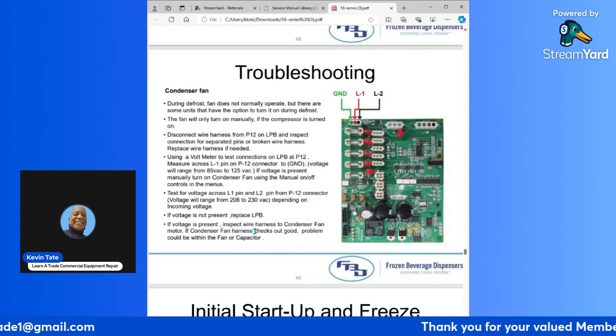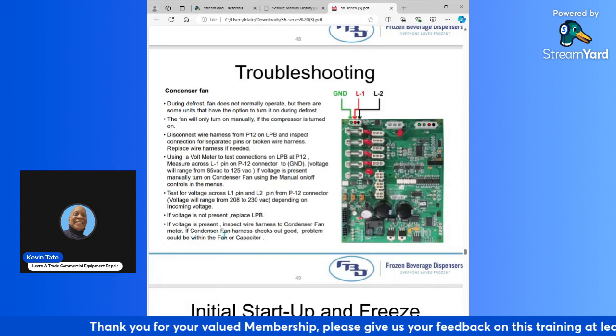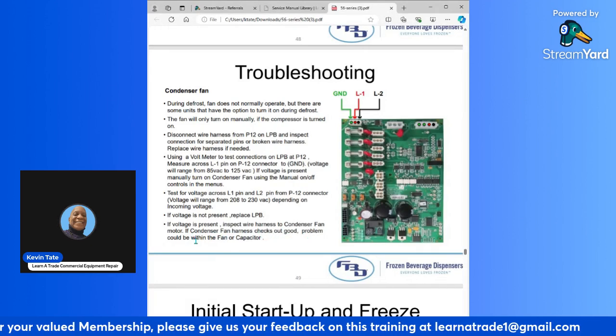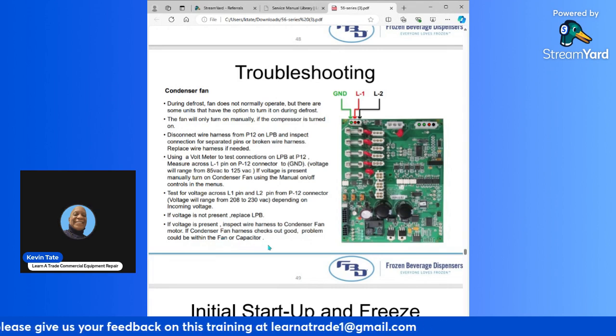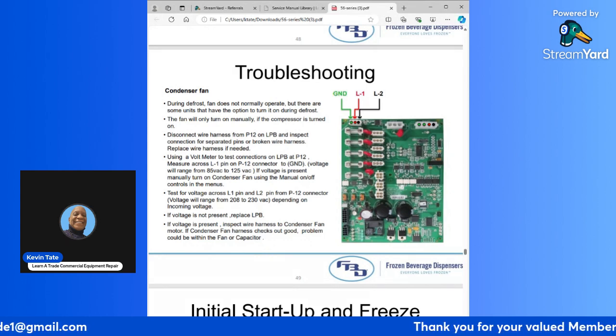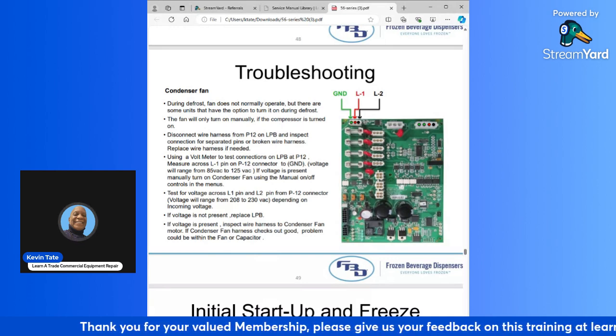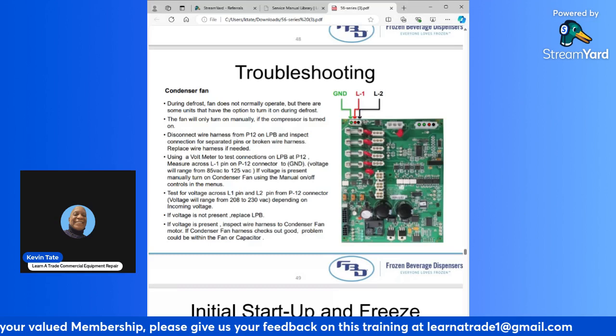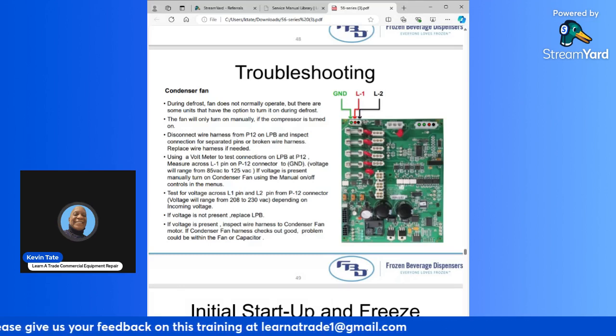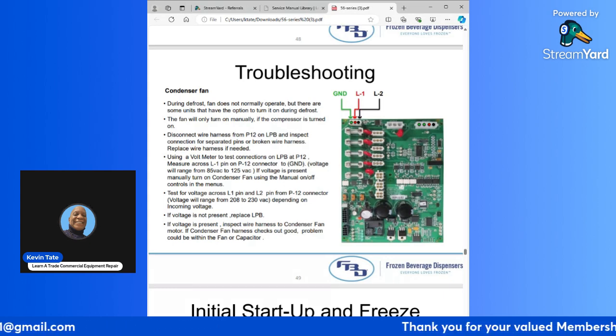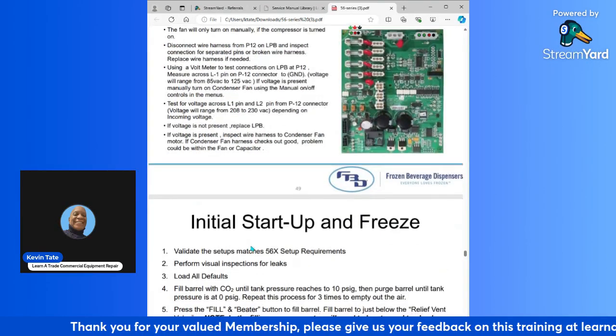If voltage is present, inspect the wire harness for the condenser fan motor. If the condenser fan harness checks out good, the problem could be within the fan or capacitor. So if everything else tests good, your voltage is present, and you inspect the wires and they all seem good, you could have an issue with the fan itself. The motor shaft could be bound, or you could have an issue with the fan capacitor, in which case you could just change out the capacitor, and that would enable the fan to work.